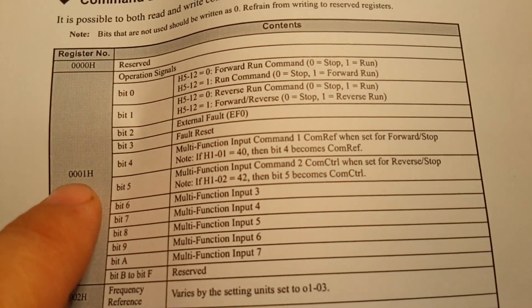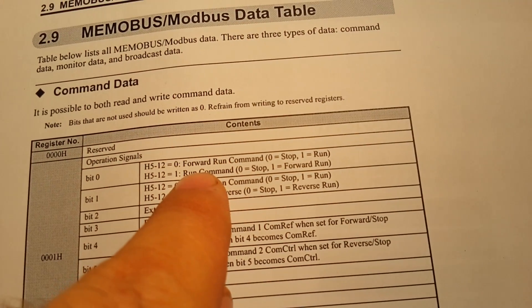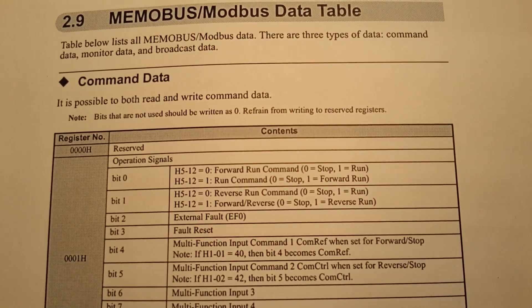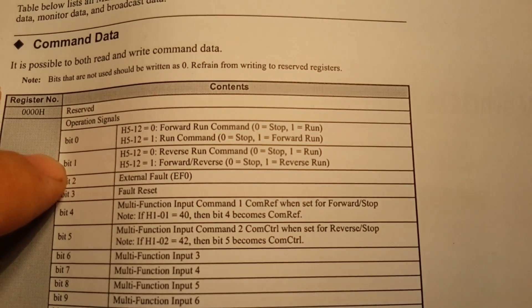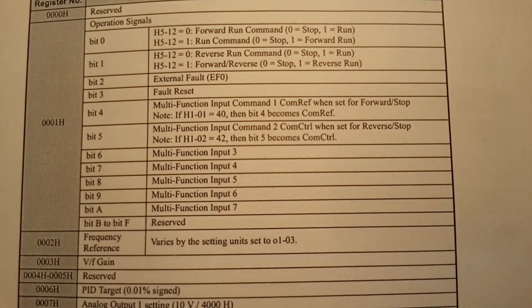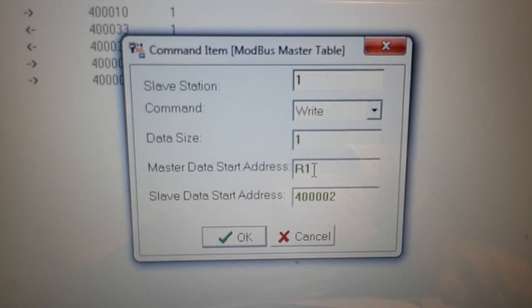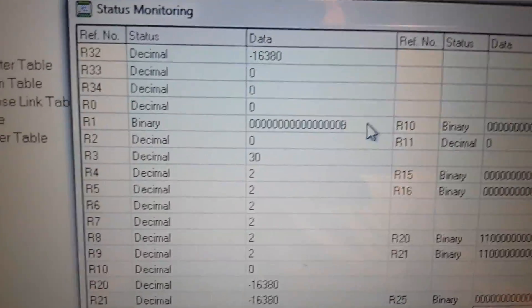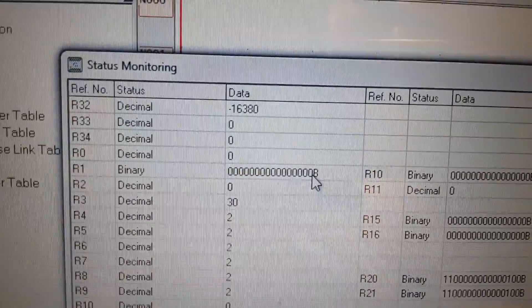The command value is 0001 hexadecimal. Each bit has a function: the first bit is the forward run command, and the second bit is the reverse run command. We type the master data start address to R1 — this R1 has bits, and the first bit starts the frequency inverter. This is the R1 command.